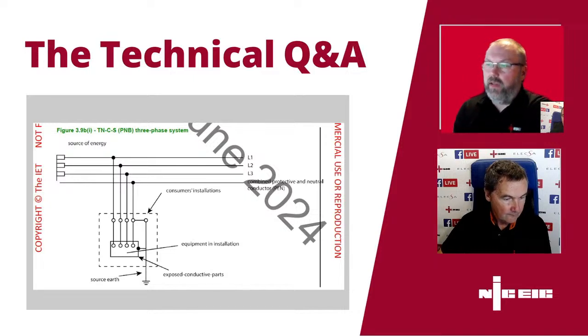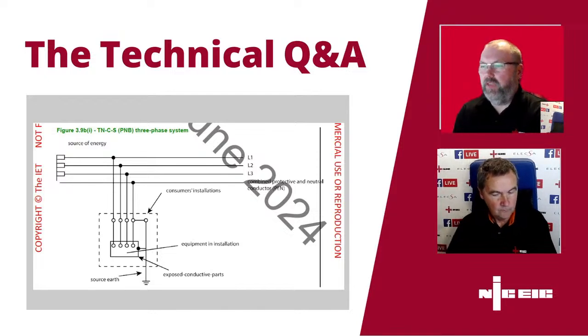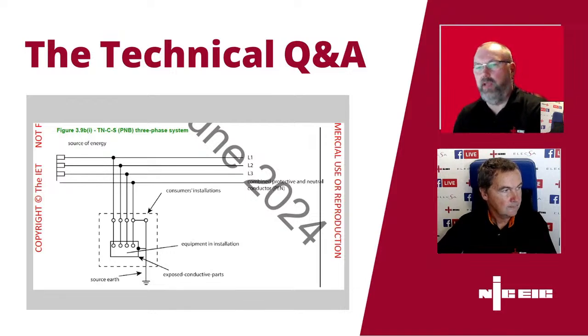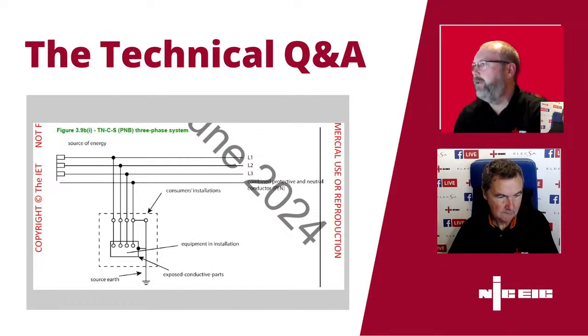Yeah, it's something I've had a few times in the past, some questions on the technical helpline. The difference is a PME is a protective multiple earth, which has connections all along the route from the transformer to the premises, with multiple connections generally at a maximum of 40 metres between them - that's why that 40 metres is referenced. Also, for additional information, if anyone wants to go onto the Energy Networks Association for G12 - I think it might be edition 4 now, or amendment 5 - it gives good explanations about different earthing arrangements. A really valuable document.